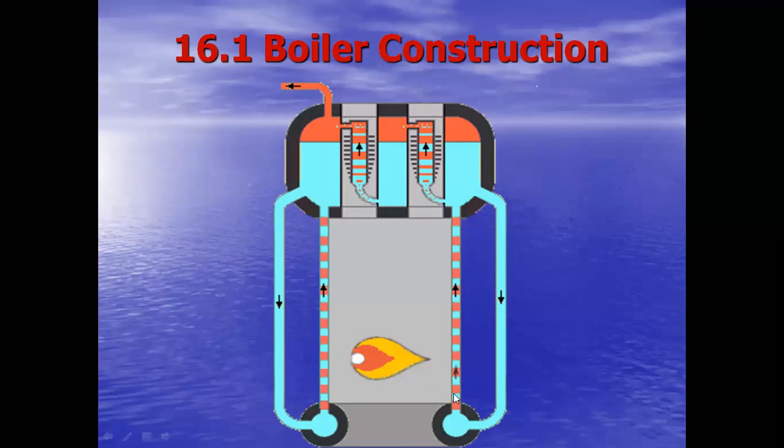The water in these water tubes is heated by this flame from the burner. The water and steam rises and goes to the steam and water drum. And here, this is where the hybrid part comes in. Here also you have the water and steam drum, which has got these holes, the tubes through which the smoke passes. So here it becomes kind of a smoke tube boiler, and inside these tubes you have these so-called pin tubes or sunrod tubes, as they used to be called in the trade earlier.